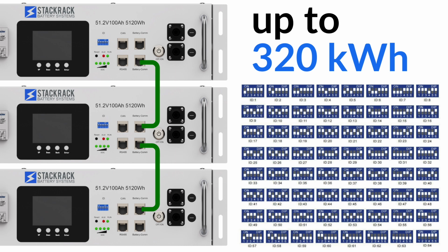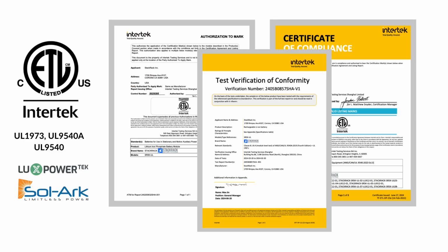Each battery module features a 6-switch ID with battery-to-battery communication terminals using standard Cat5 cables. This allows us to address and maintain active communication with up to 64 battery modules or 320 kilowatt hours. So this allows you to build out a very large battery bank and still maintain inverter and battery-to-battery communication throughout the entire system.